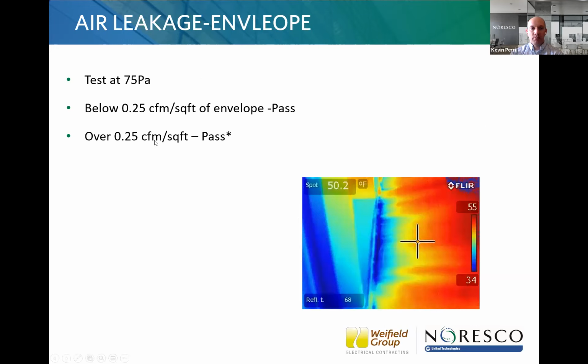So again, testing to the same Pascal passing limit. We already talked about that. The one thing I want to point out here is the asterisk. If you're following the 0.25 CFM passing rate, and you're over that, a diagnostic evaluation still needs to be conducted along with a visual inspection. Then repairs need to be made, and it has to be retested. So that's an addition to anything that we've heard so far, where usually you just have to fix or address those items, say what you addressed, and then submit that to the owner and building official. In Fort Collins, you actually have to do a retest and then submit your report to the building owner and the building official. They don't want to see that report if it's failed until repairs have been done and a retest has been conducted as well.